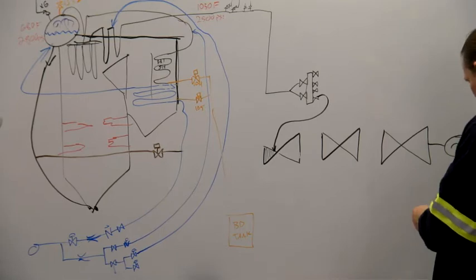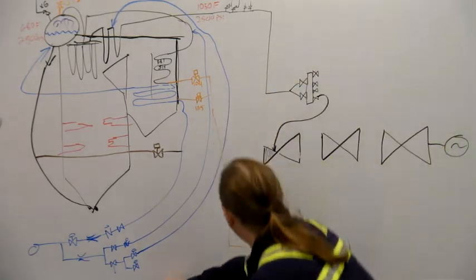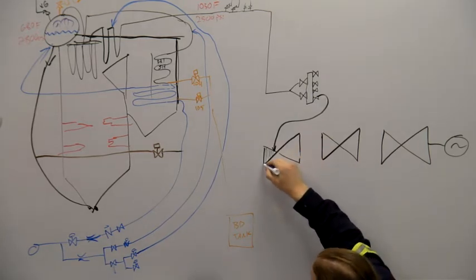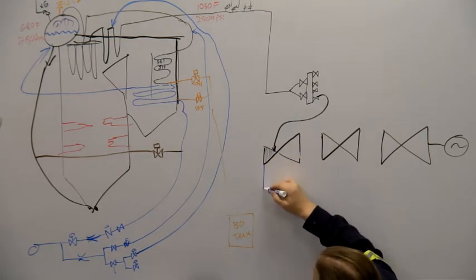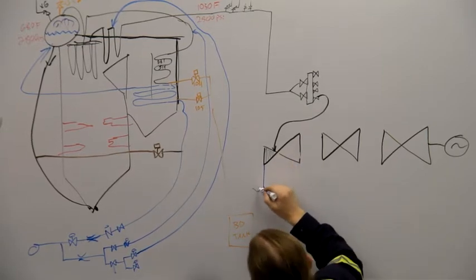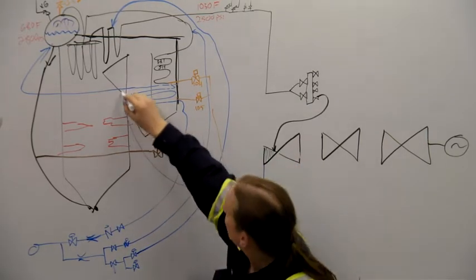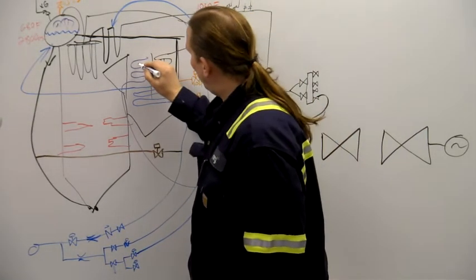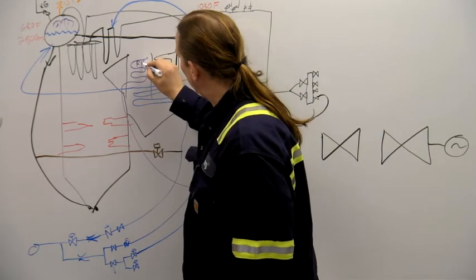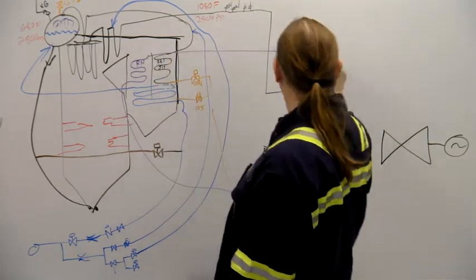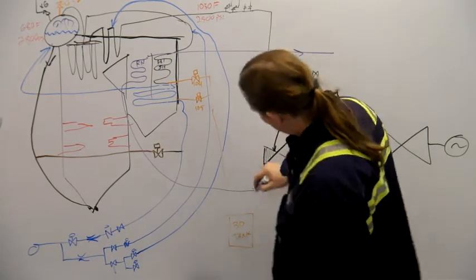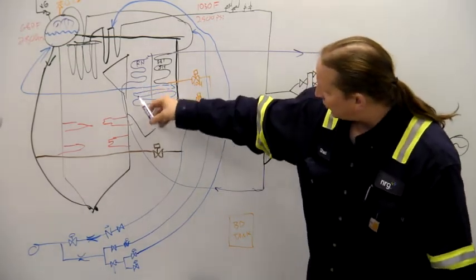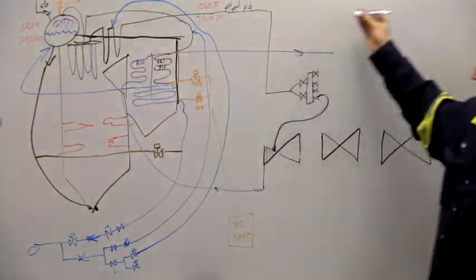So we go through seven stages of the HP turbine and then we come out the bottom. The exhaust from the HP turbine goes back into the boiler and gets heated up. This is called the reheat section. Before it goes back to the boiler it's called cold reheat, when it comes out of the boiler it's called hot reheat.